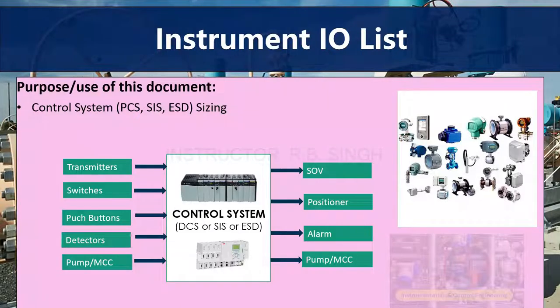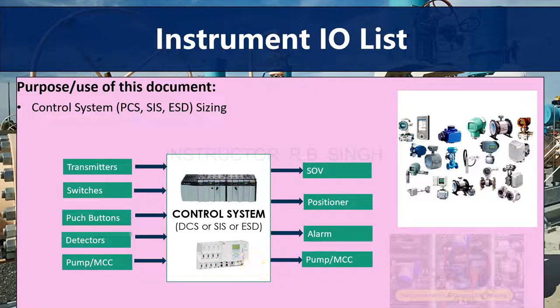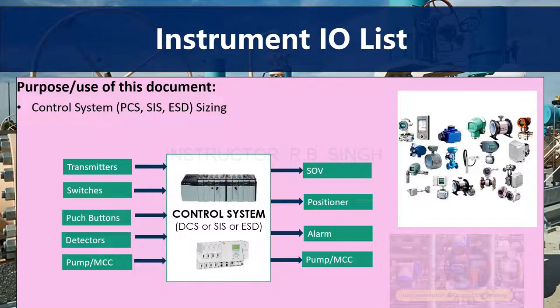Regarding the purpose and use of this document: our complete plant will be controlled by a control system — either PCS (Process Control System), SIS (Safety Instrumented System), or ESD (Emergency Shutdown System). Whenever we do the sizing of the control system, the IO List will be required. Without the IO List, we cannot size the control system. For example, to calculate the number of IO cards — for AI, AO, DI, and DO signals — we need the IO List, as IO cards have different capacities.